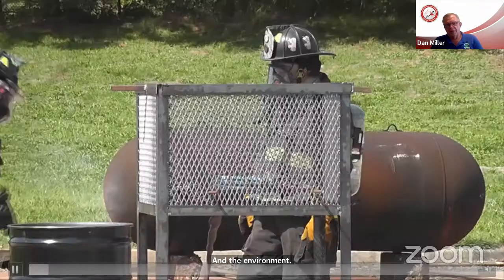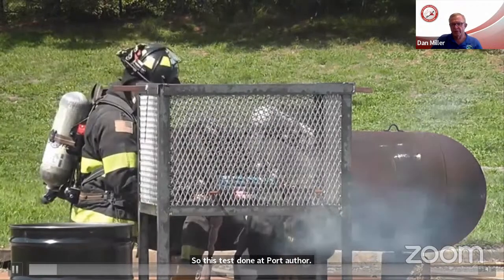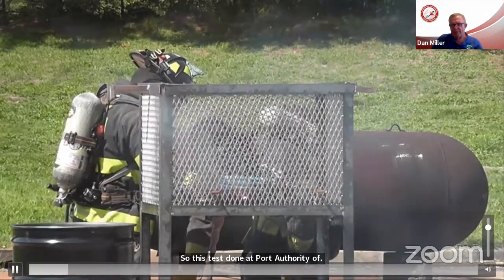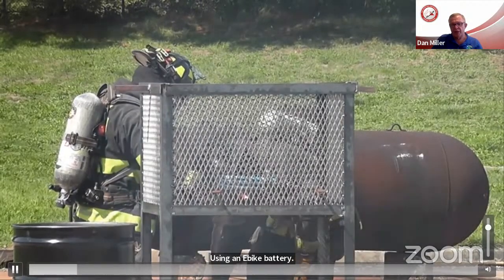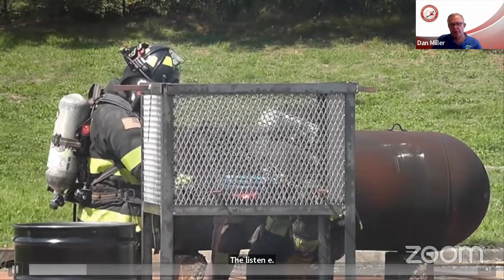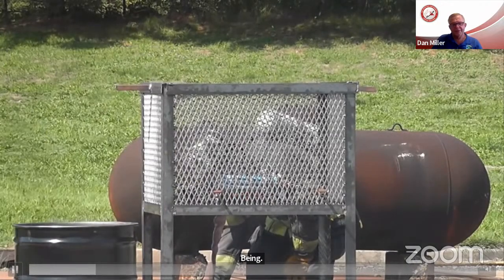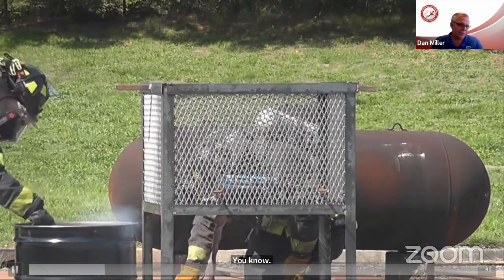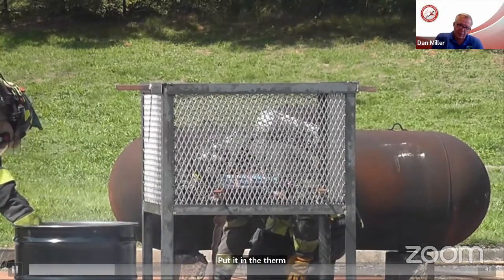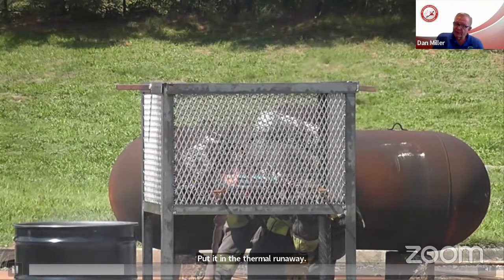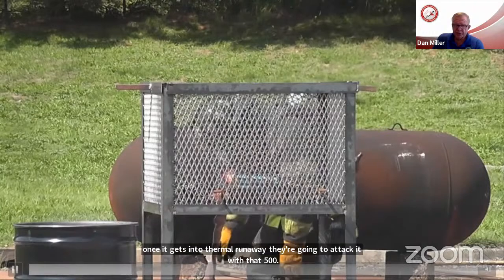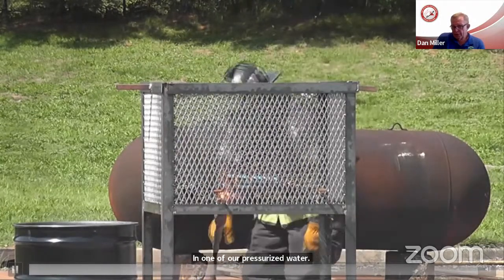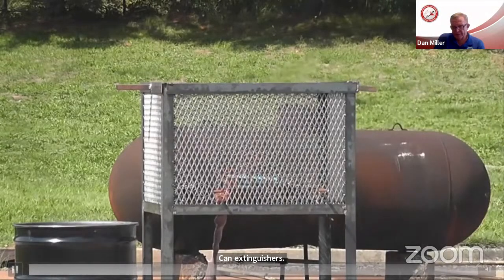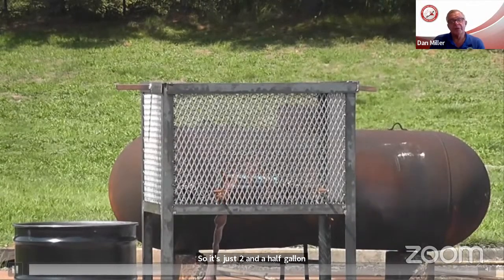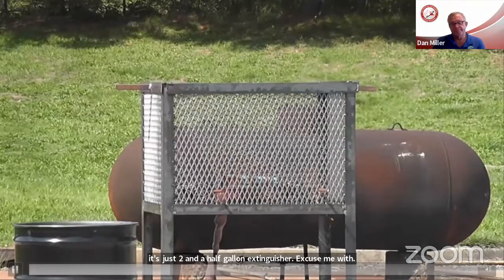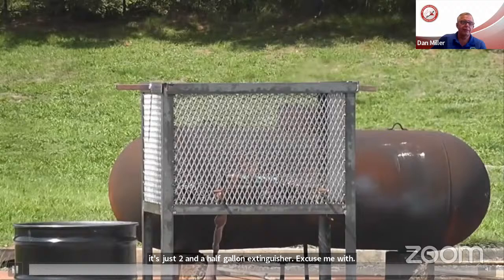This test was done at Port Authority of New York and New Jersey, using an e-bike battery in a cage, being heated up by a turkey fryer beneath it. They warm it up, put it into thermal runaway, and once it's in thermal runaway, they attack it with F500 in one of our pressurized water can extinguishers—just a 2.5 gallon extinguisher with 3% F500 inside.